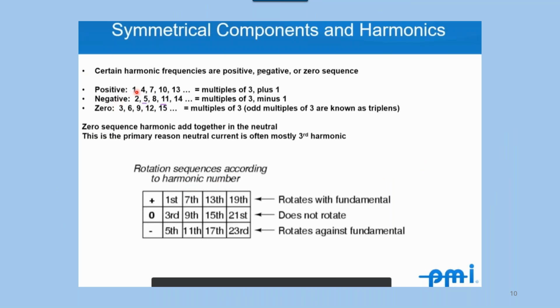So what you've got is all the different harmonics. If you see the first, fourth, seventh, any of them that's a multiple of 3 plus 1, that's positive sequence. Positive sequence, if you know anything about symmetrical components, is good, because that's what we want. Negative sequence is going the wrong direction. Negative sequence is fighting against the rotation we want. And that's all the multiples of 3 minus 1.